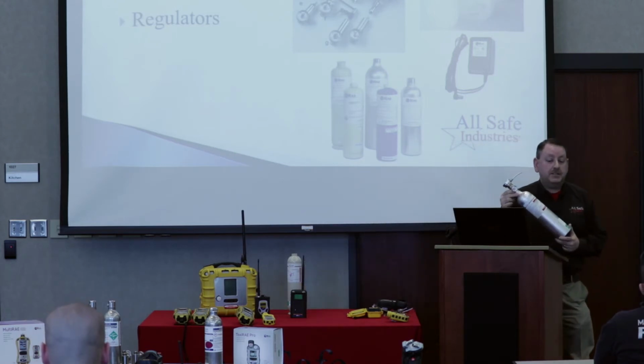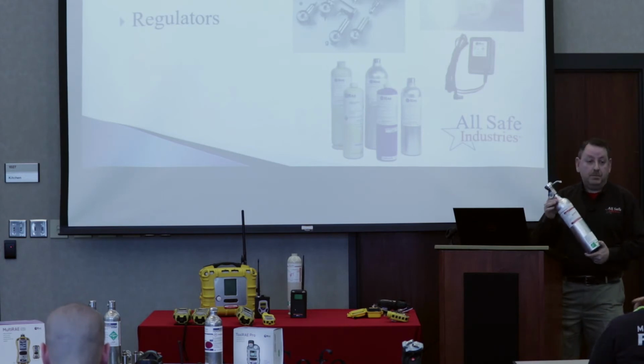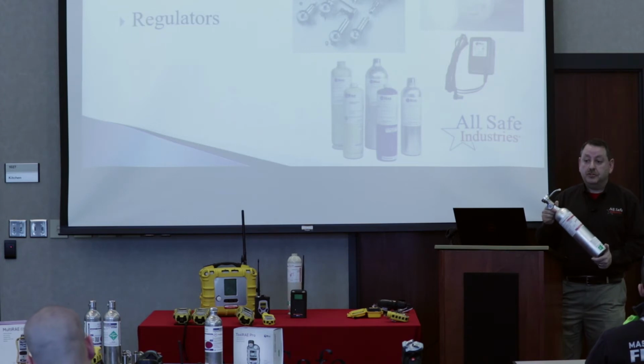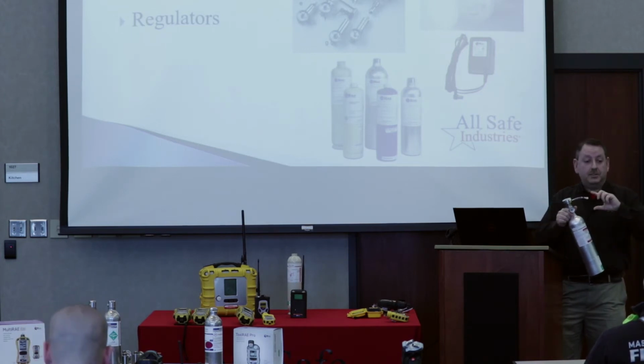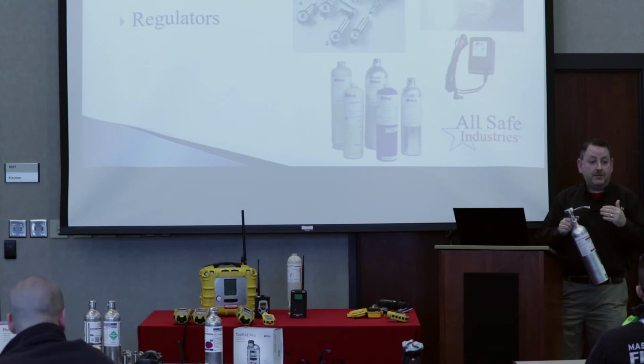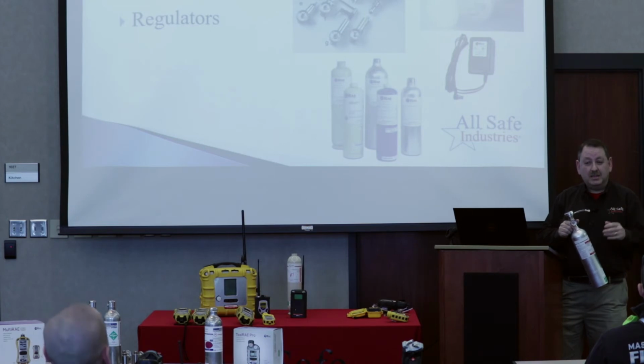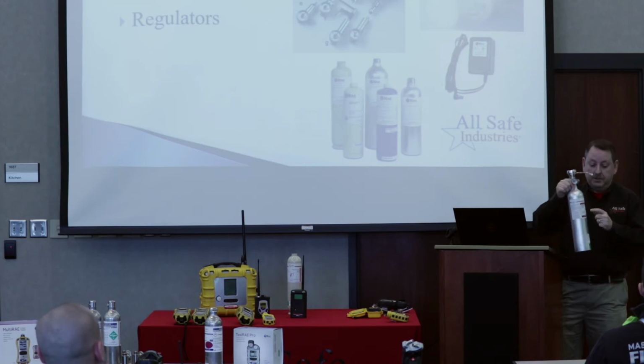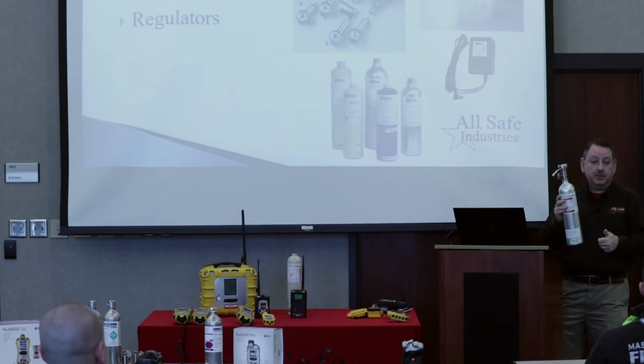The calibration gas is what you're going to use to do a bump check to make sure that the sensors are working. And again, oftentimes you're just going to do that in real runtime. So the meter's running, you'll attach it to the cylinder of gas, you'll watch the sensors react. As soon as you're satisfied they reacted sufficiently, so I like to say about within 20% of the numbers on the side of the cylinder, you're good to go.